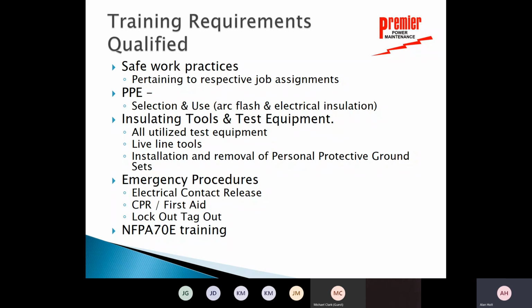We don't do a very good job of that sometimes, but basically, you need to be trained on each piece of equipment that you're going to operate. You need to understand the ratings of that piece of equipment. When you're wearing low voltage gloves, what's the voltage rating of those gloves? When you use your Fluke meter to take a voltage reading, you need to understand the ratings of that Fluke meter. Is it 1,000 volts rated? Is it 600 volts rated? Is it Cat 3? Is it Cat 4? You're required to know that. If you're using a hot stick, what's the rating of that hot stick? Every piece of equipment, you need to have some training on how to use that equipment and what the ratings of that equipment are.